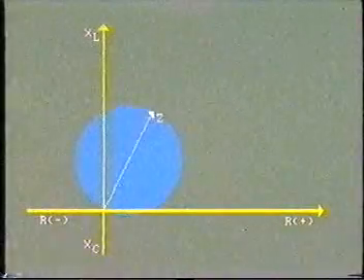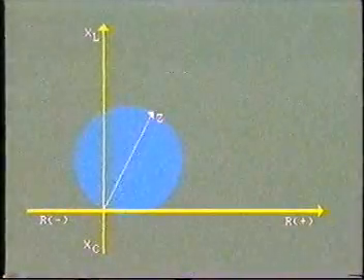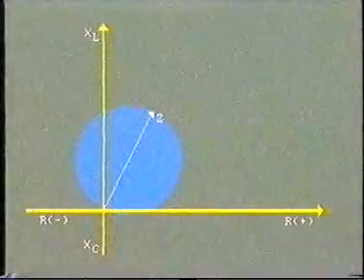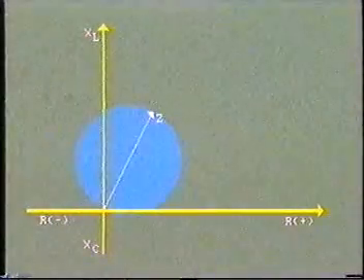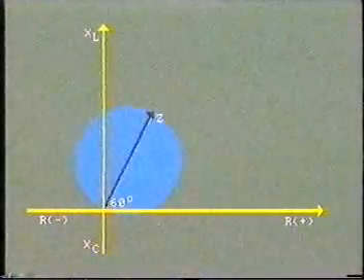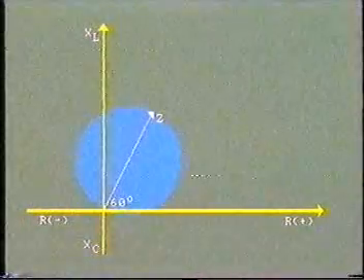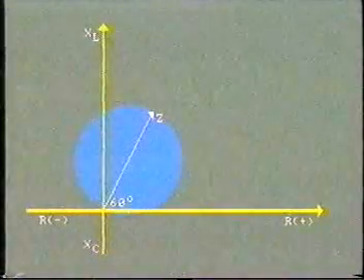The main feature of this relay is that maximum closing force occurs when the impedance is at a specific phase angle, usually about 60 degrees. This is similar to the phase angle of the line conductor impedance.